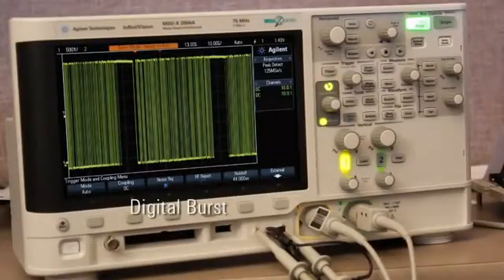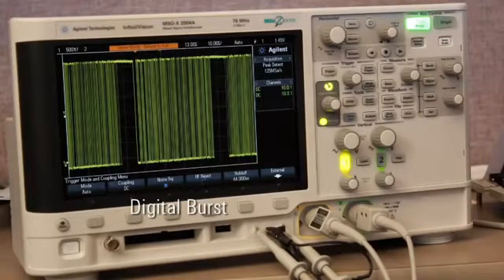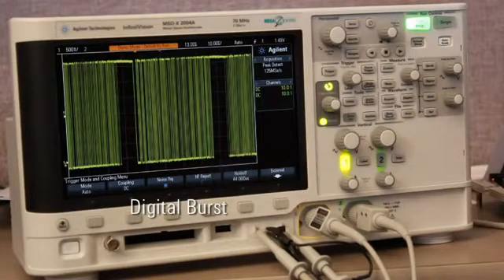The digital burst training signal is used to teach students how to use trigger hold-off in order to trigger on a complex burst of signals. This is a concept that even many experienced engineers don't understand.